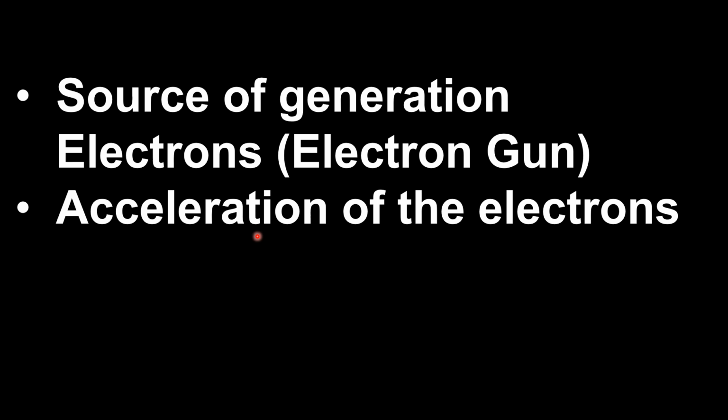So in continuous X-ray devices, initially a source is used to generate a stream or beam of electrons, and that source is known as the electron gun. From the electron gun, the electrons are accelerated by a combination of different types of pre- and post-accelerating anodes and a Wehnelt cup. After that, the stream or beam of electrons is bombarded on a metallic anode.